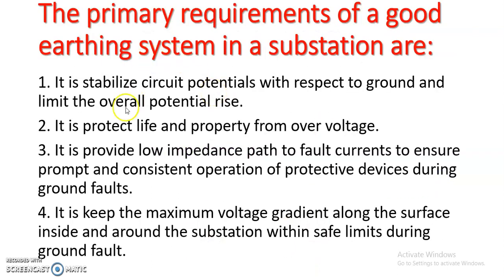So these are the primary requirements of good earthing system in case of substation. So it stabilize the circuit potential with respect to the ground and limit the overall potential rise. Then second point is it protects the life and property from the overvoltage. Then third, it provides the low impedance path for the fault current. Then fourth is it keeps the maximum voltage gradient along the surface inside and around the substation within the safe limit during the fault occurrence. So these are the some primary requirements of good earthing system.